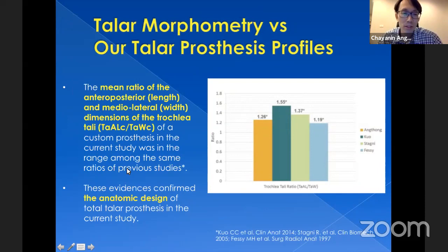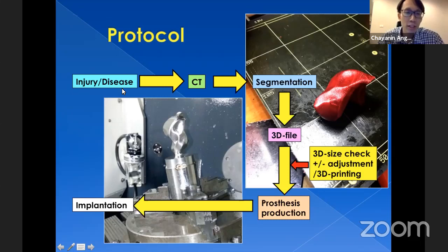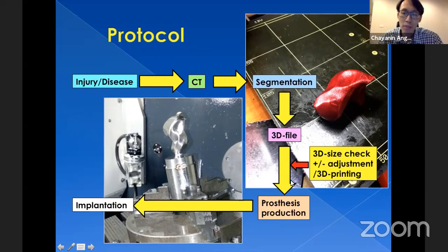These findings confirm the anatomic design of the total talus prosthesis. For the protocol, when I identify a case needing talus prosthesis replacement, I send the CT of the contralateral talus and have my engineer do the segmentation — converting the DICOM CT data to a 3D file. Then we apply the mirroring technique using CAD, check the size, and adjust the shape. We can also do 3D printing to verify the size and shape. When satisfied, we proceed to prosthesis production using CNC — computer numerical control milling based on the 3D file — and then implantation after sterilization.